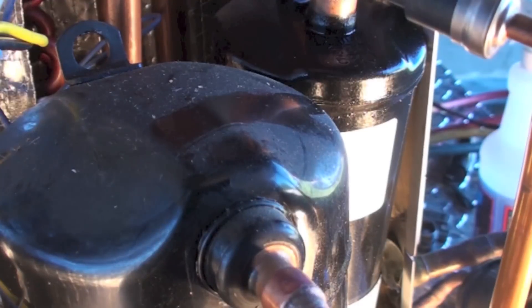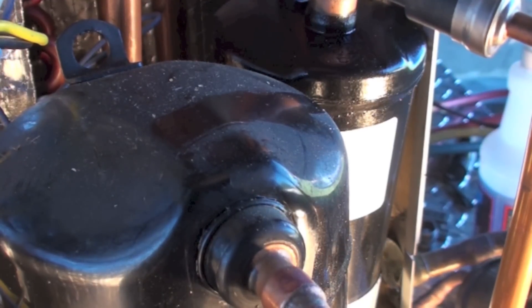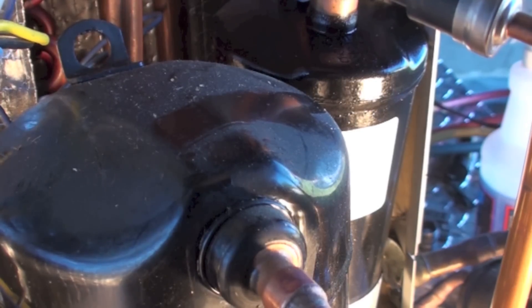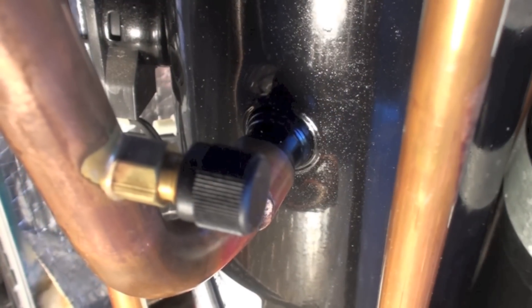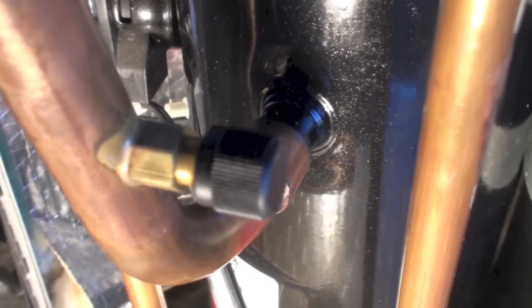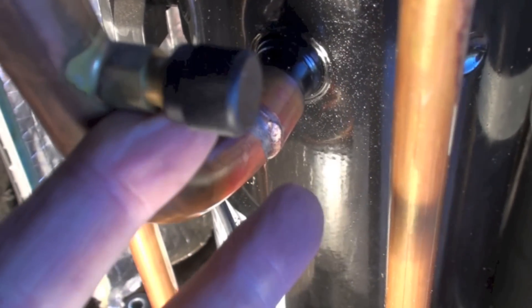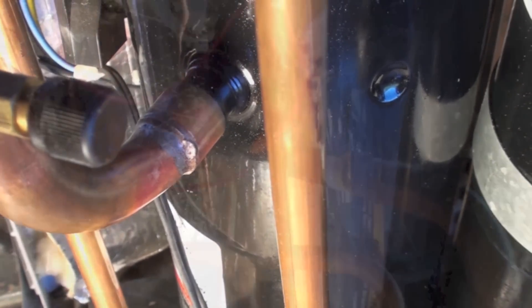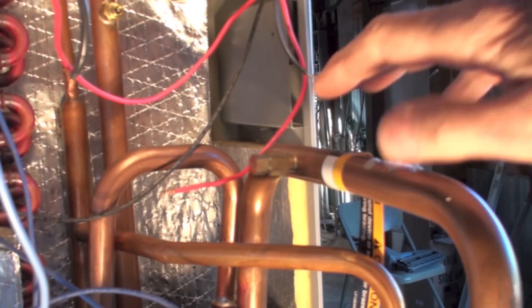Right here at the top of the compressor, it also has some oil on it. One of the other things I like to look at is the service ports — there shouldn't be a lot of oil on this thing, and I don't see much, just maybe a little bit in there, but that could be from when they put gauges on and took them off.